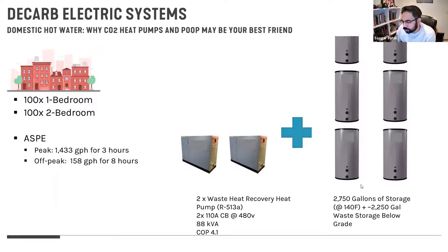So any issues with fouling on the wastewater heat exchangers that you'd be concerned of? Absolutely. Biologic biofilm fouling on heat exchangers for wastewater heat pumps is probably the number one failure point for those systems. There's a couple different companies in this arena. One of them uses a tube and shell heat exchanger with a mechanical device that scrapes the tubes in the heat exchanger on some period. And then others use a backflush strategy throughout the day to wash off the heat exchanger.